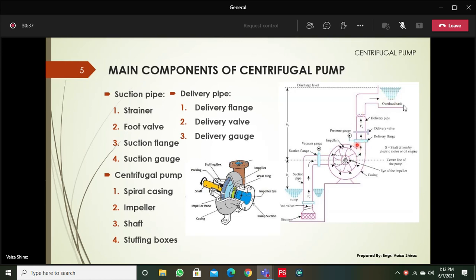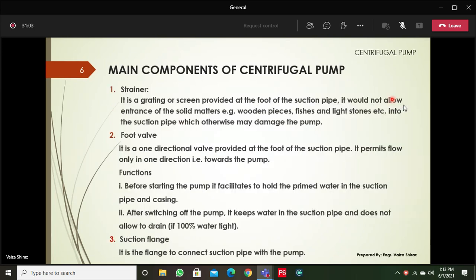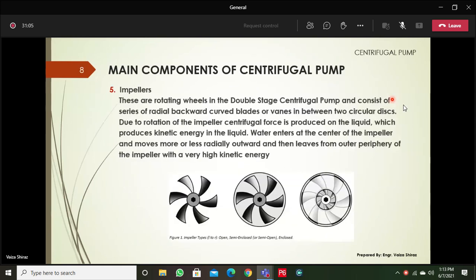In the delivery pipe, we have the delivery flange, which is the connection between the delivery pipe and the main pump, and the delivery gauge which measures positive pressure on the delivery side. Then we have the delivery valve which regulates flow on the delivery side. Finally, through the delivery pipe, water is delivered to the overhead tank or higher elevation. There is one more component we have not yet discussed — the stuffing box.